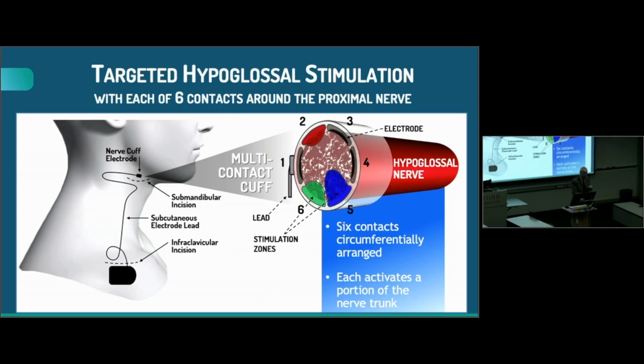It too has a pacemaker can, it has a lead body, and a circumferentially arranged electrode over one of the hypoglossal nerves. But as shown here on the left-hand side, there are 6 contacts, each of which can be stimulated at different levels of juice, of stimulation energy, however you want to define that, in order to activate a specific portion of the nerve. And so that creates a sort of therapeutic titration nightmare. The degree of flexibility or permutations that you have between titrating 6 contacts at different levels of stimulation becomes insurmountable inside of a single night of study.